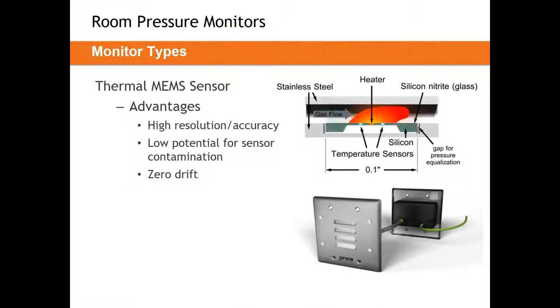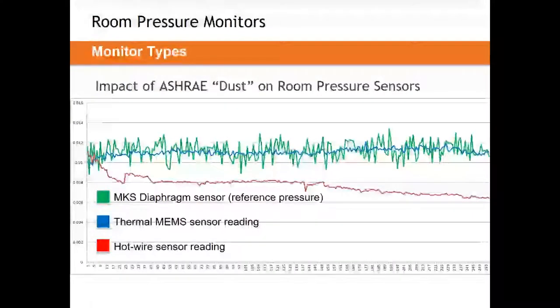Unlike the hot wire anemometer, which needs to be cleaned because airflow passes through the device, a thermal MEMS sensor has its temperature sensors and heating elements encased in a silicon wafer, pulling them out of the airstream so they don't physically collect lint, dust, or dirt. And unlike the hot wire anemometer, there's no risk of drift because there's nothing to physically change, stretch, or move. What you get with a thermal MEMS sensor is a maintenance-free device.